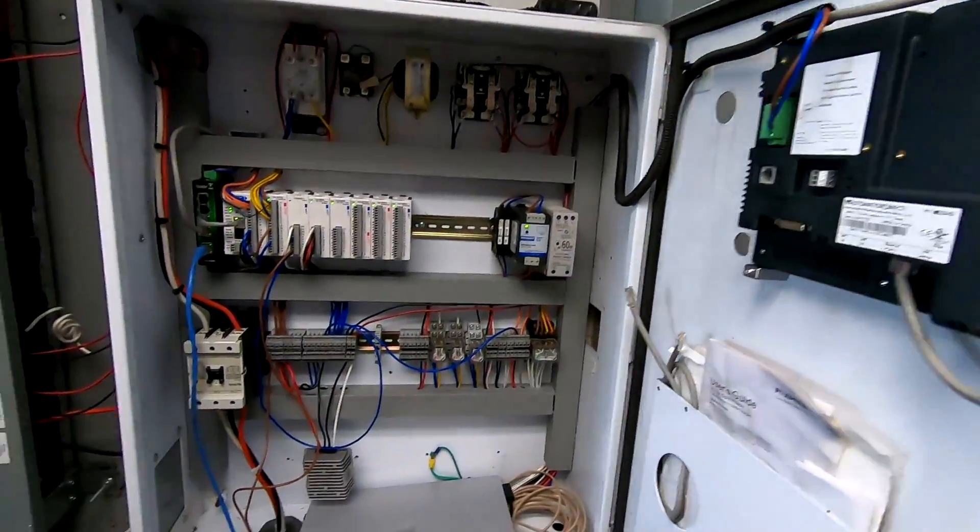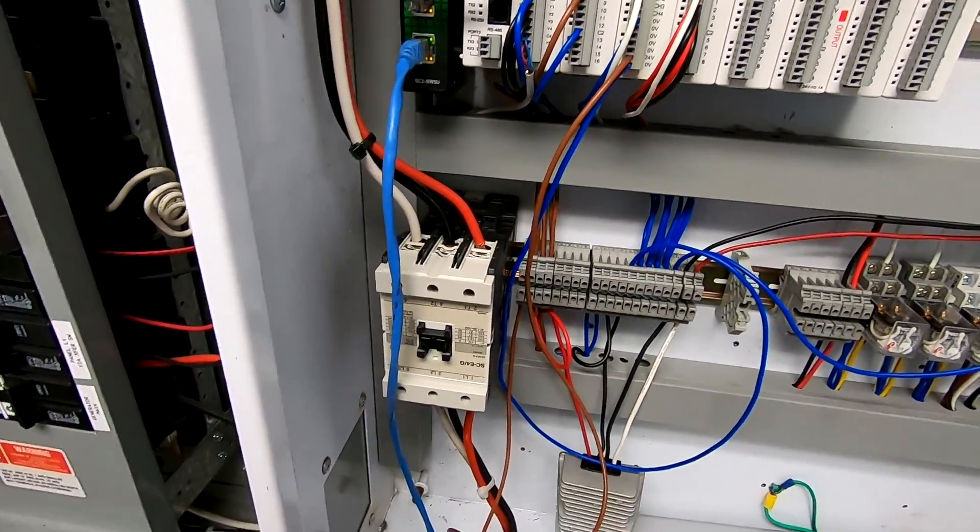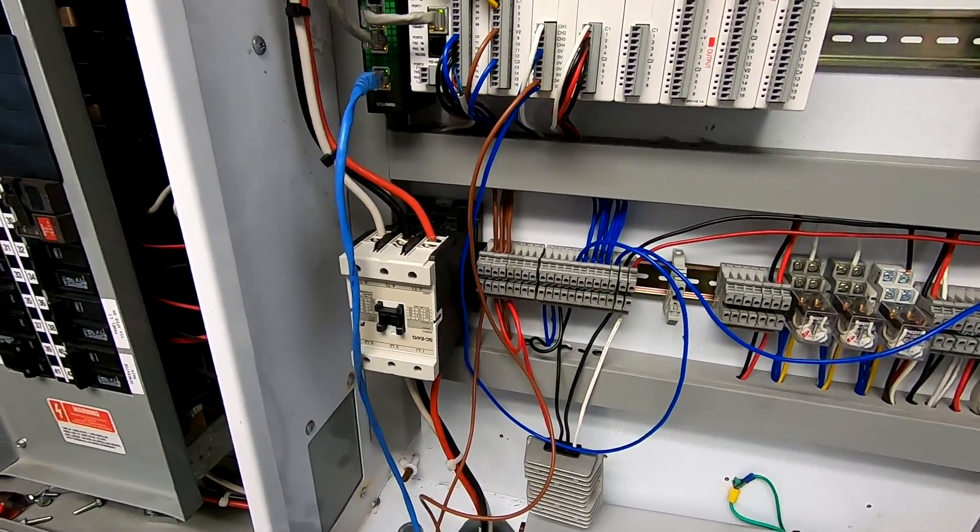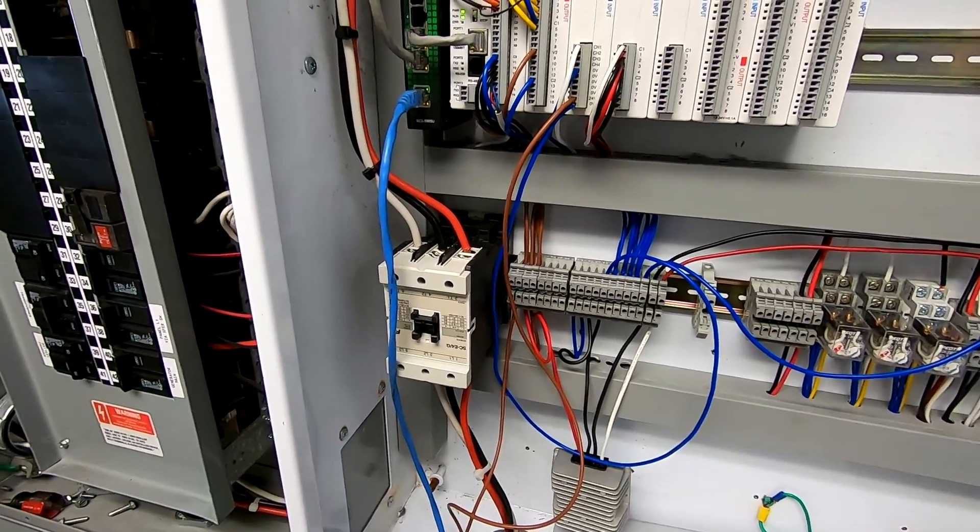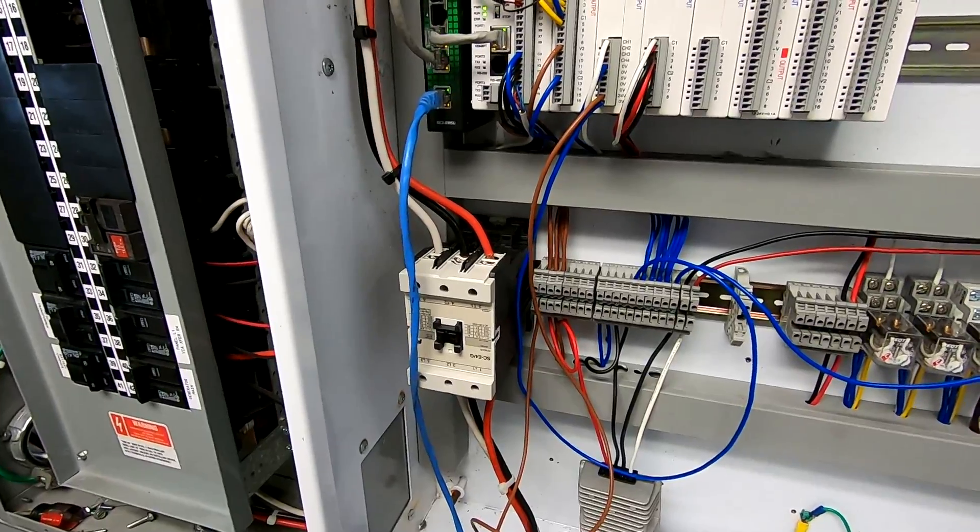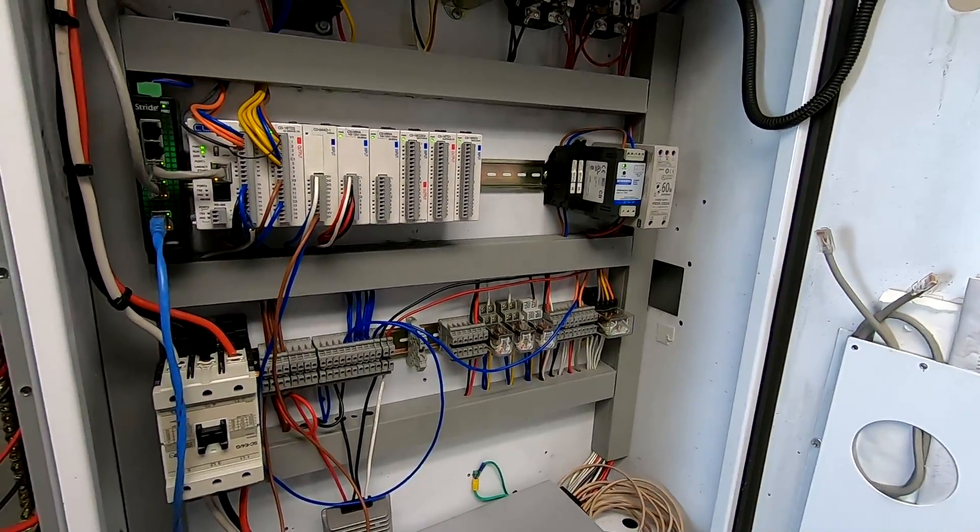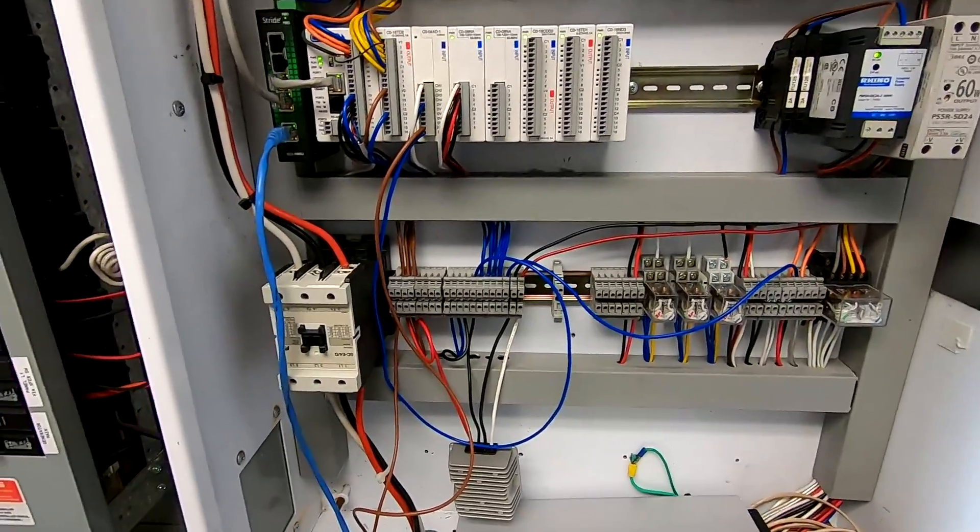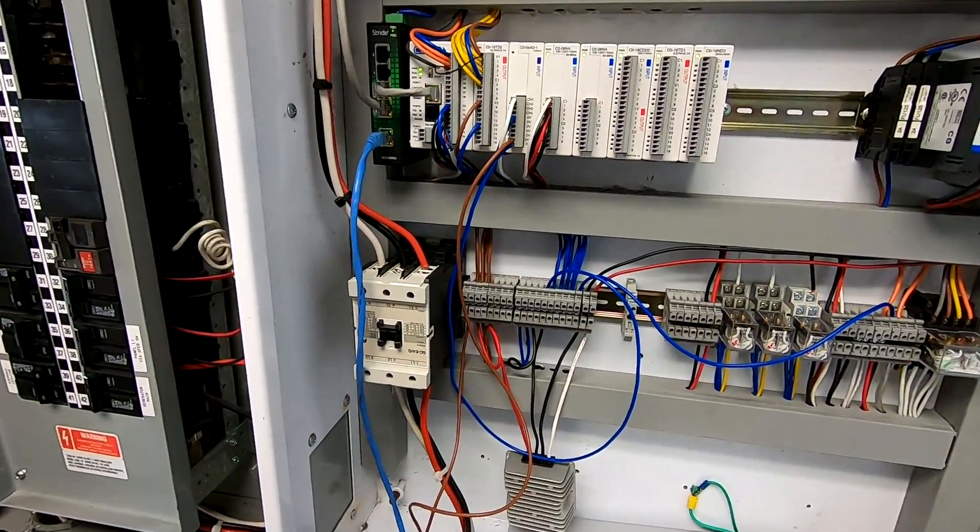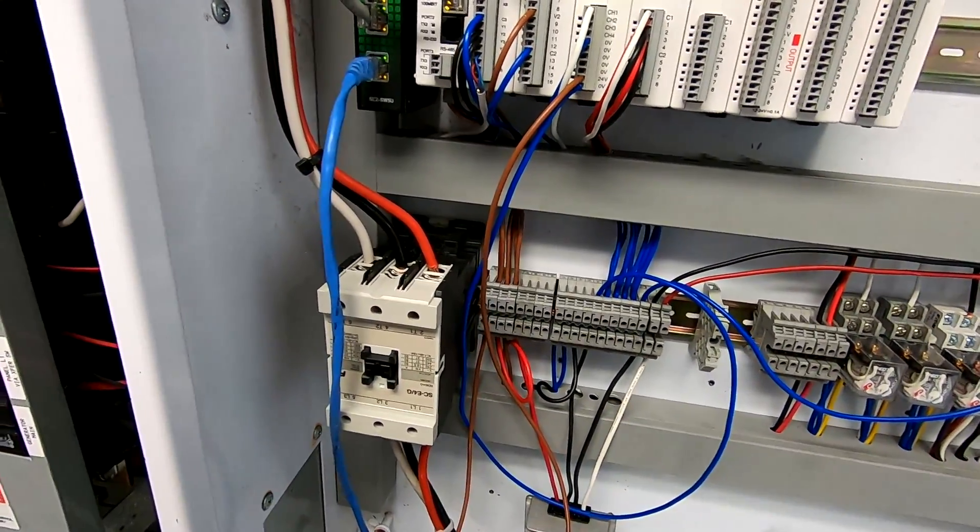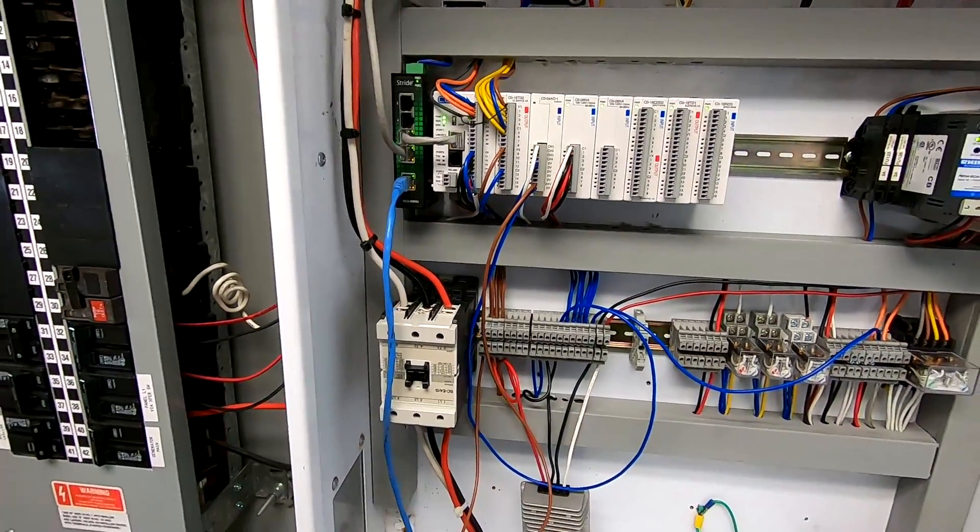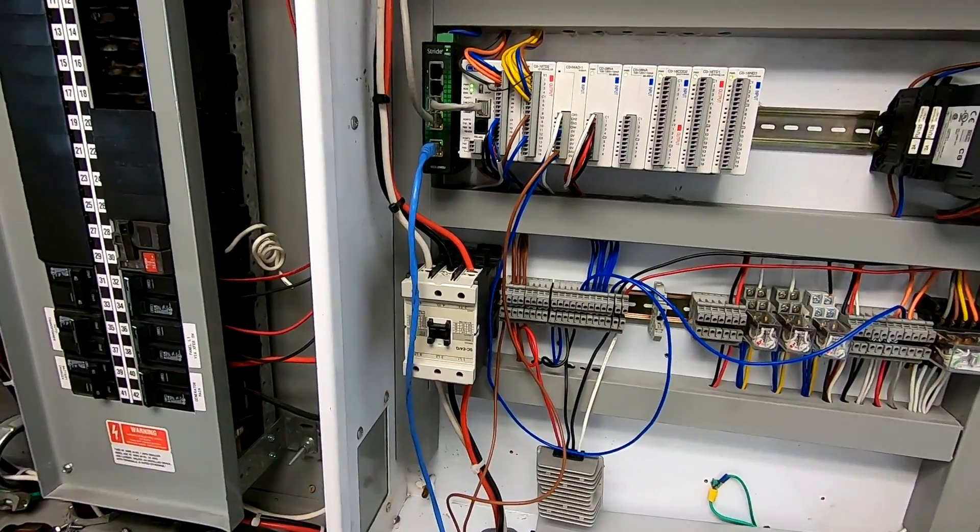I got my contactor in my control cabinet changed. This has a 24 volt DC coil now, instead of the 24 volt AC coil I had prior. And the problem was with the 24 volt AC coil, when the power would go out, I would no longer have power to close the contactor. And since now I'm running off the DC to DC converter, which is straight off the battery bank, if the voltage does get too low and the inverter shuts down, I should still be able to transfer enough power to this contactor and engage the generator and start the battery. So that was something. This was on Automation Direct, it was about 120 bucks for the contactor, and I have the surge suppressing module on the bottom. But definitely something that I needed a long time ago, and shouldn't have delayed this long on. But it's there now, and things are running happy.